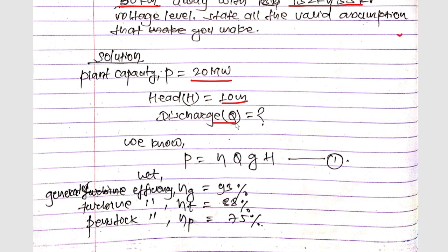To determine the discharge, we use the formula P = η × Q × g × H. The efficiency is not given, so we assume generator efficiency as 93%, turbine efficiency as 88%, and penstock efficiency as 75%.